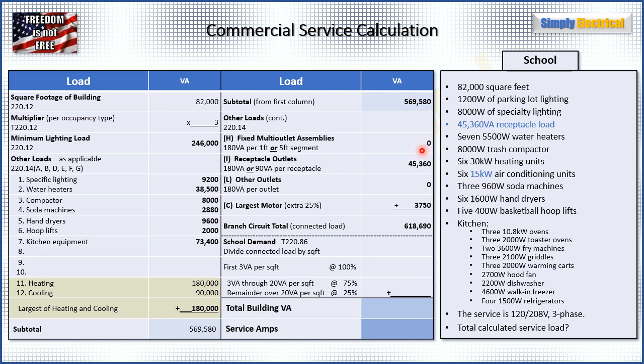Continuing with other loads from 220.14: fixed multi-outlet assemblies — we don't have any, so zero. Receptacle outlets come to 45,360 VA. Other outlets — none. Now we find our largest motor: looking through the whole building, it's one of our cooling units at 15 kW. Twenty-five percent of that is 3,750 VA. Adding our subtotal plus receptacle outlets plus the 25% largest motor premium, we get a total branch circuit load — our connected load — of 618,690 VA.